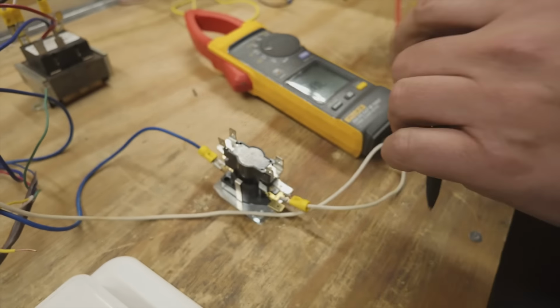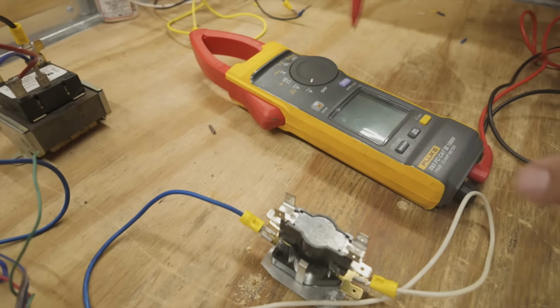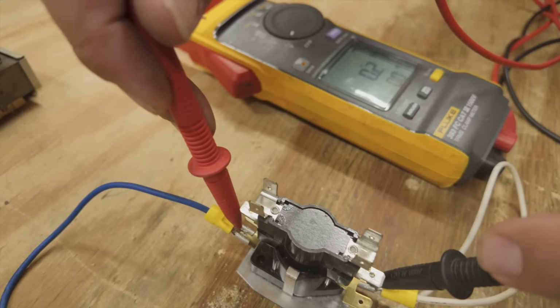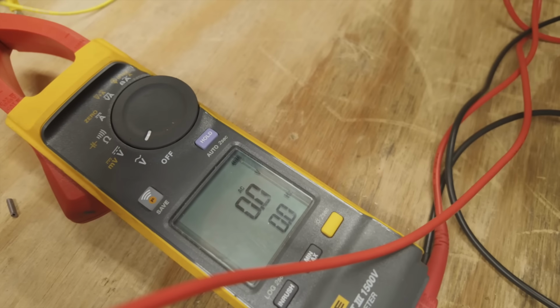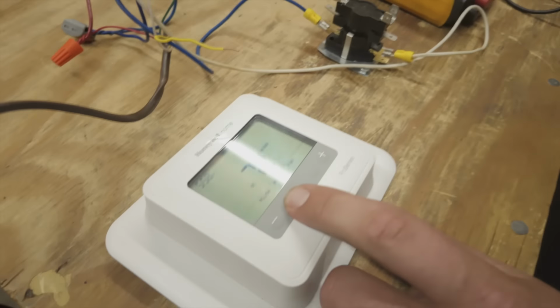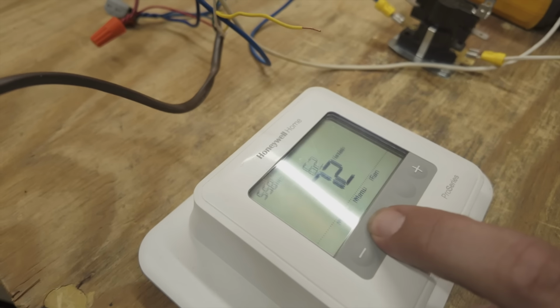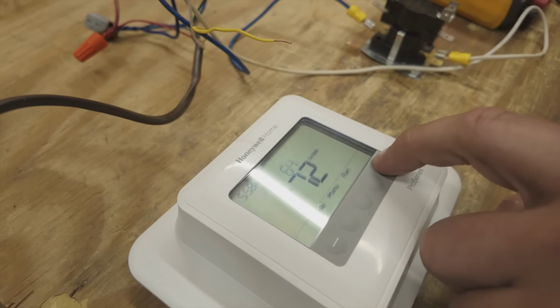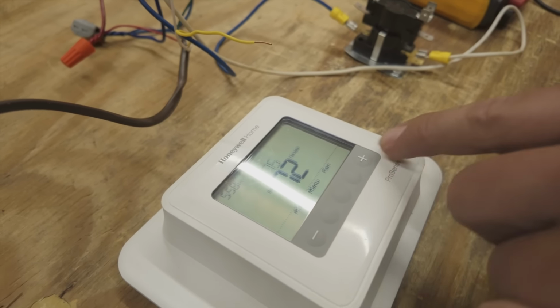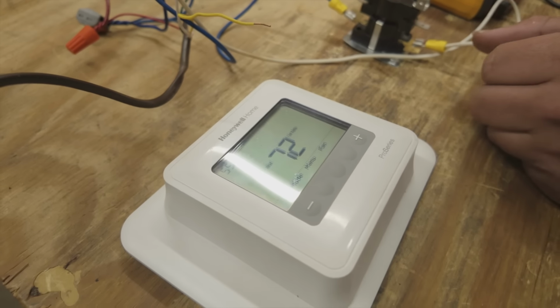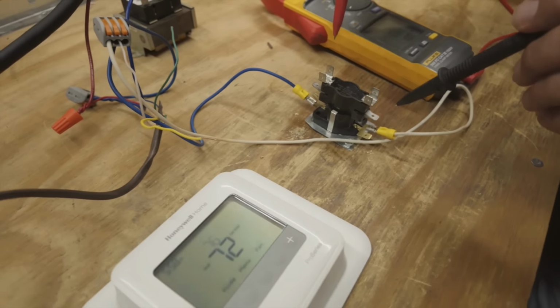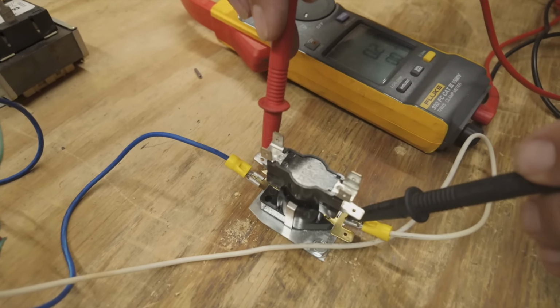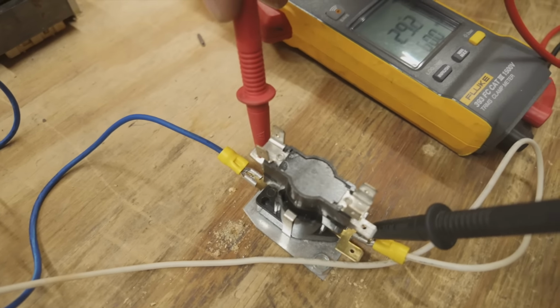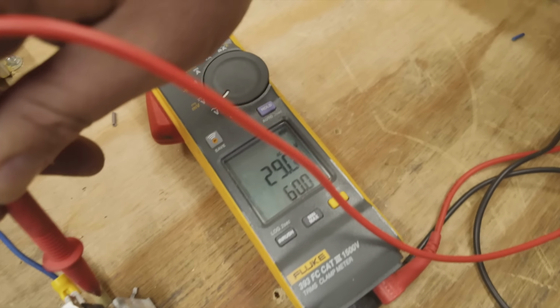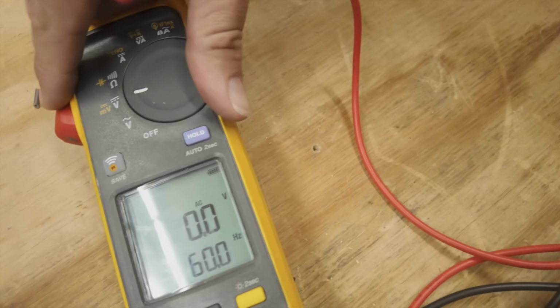When we get a call, we have to put it on volts AC and not continuity. When we get a call, those contacts are going to close. Right now we have no voltage. So we go to our thermostat, we put it on heat, turn the temp up, and hopefully there's no delay, but we're going to be able to see that we have voltage here. Oh, we got voltage. See that? 29 volts. Let's go back to continuity.